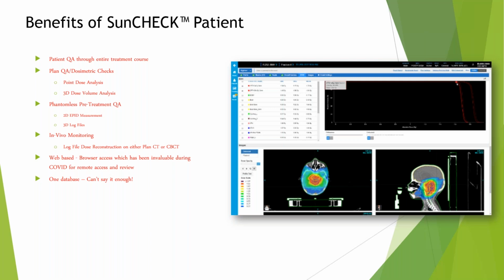Plan QA and dosimetric checks have both point dose and 3D dose volume analysis. The phantomless pre-treatment QA can be performed on the 2D EPID and also on 3D log files for recalculation of dose. In vivo monitoring can be accomplished on dose reconstruction, on either the planning CT or cone beam CT.